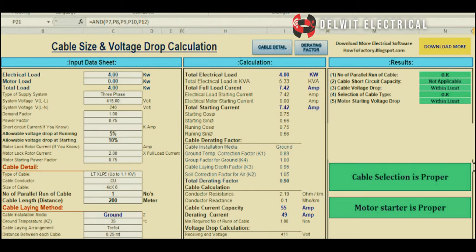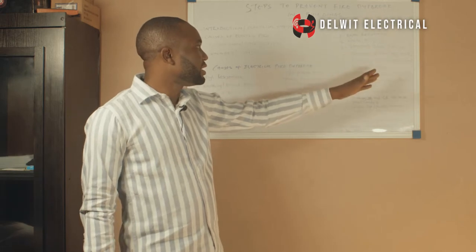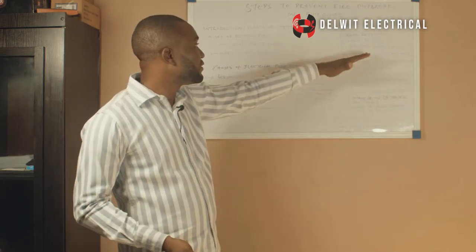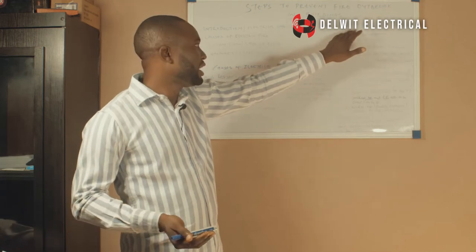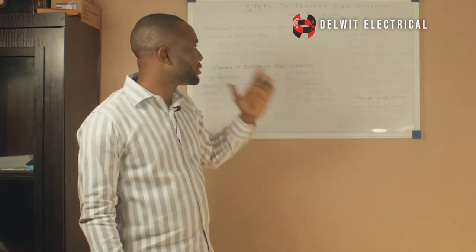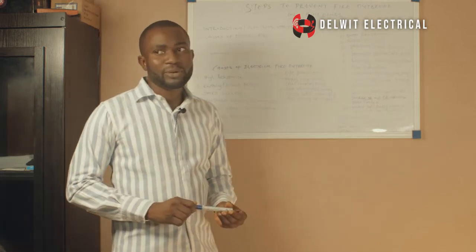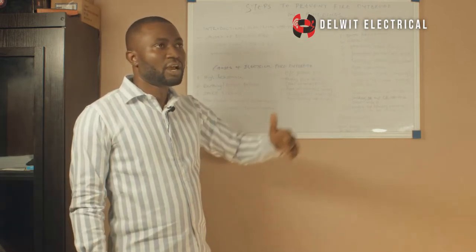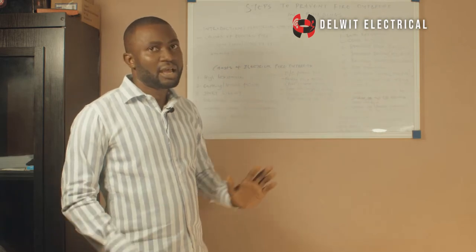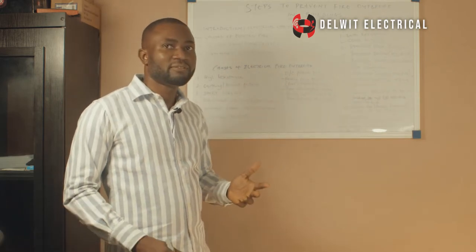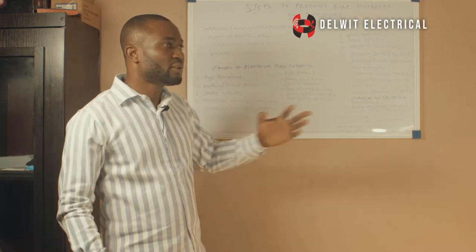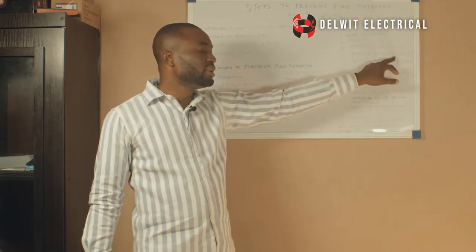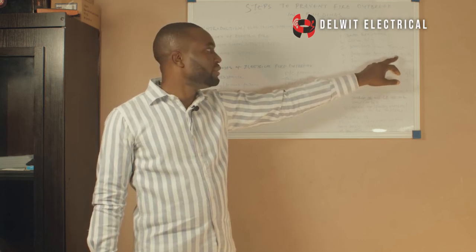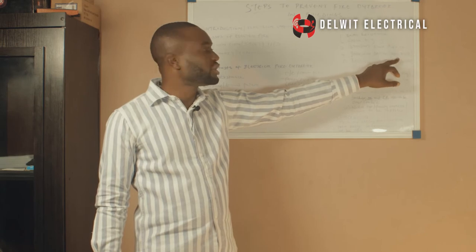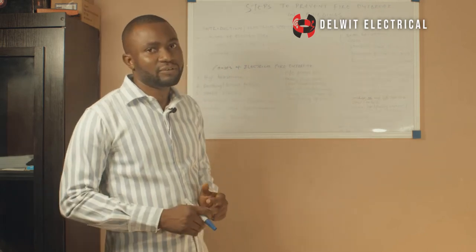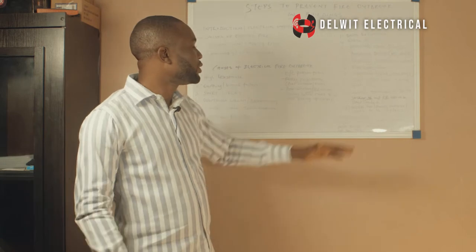Right, the third point is the standard electrical design. As I've said, it is very important. If you have a standard electrical design and it's adhered to, you cannot have electrical fire outbreak in your building. Protective devices. Most times, a lot of people get their connection directly from their cutout fuse and you go to your distribution board, which is not ideal. I always advise that there must be a protective device between your cutout and your distribution board, and I recommend a gear switch. So this gear switch is very important. So please, if your building doesn't have a gear switch, please try as much as possible to install one. It will serve as a protective device whenever there is an overcurrent trying to come into your building.